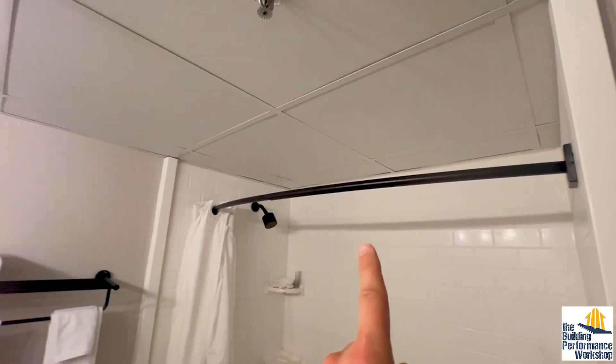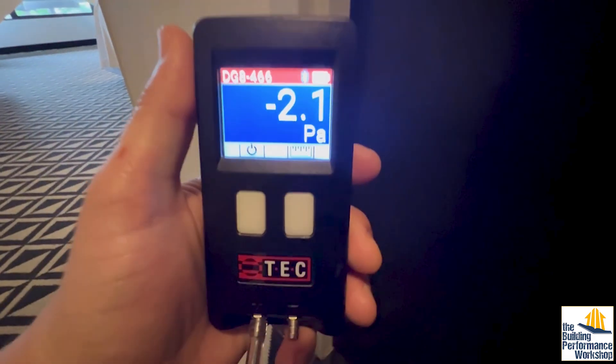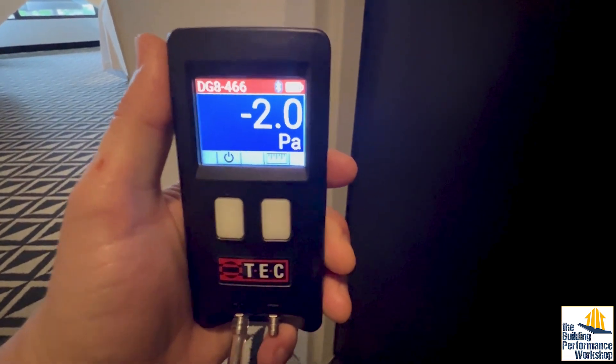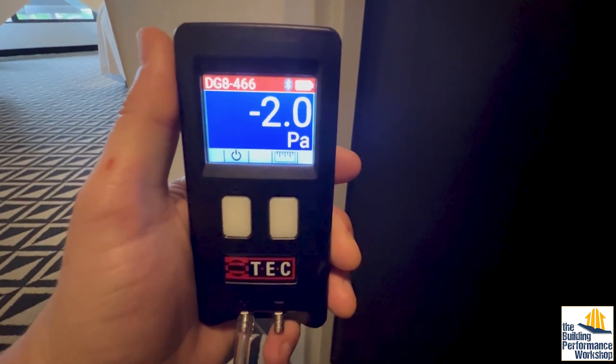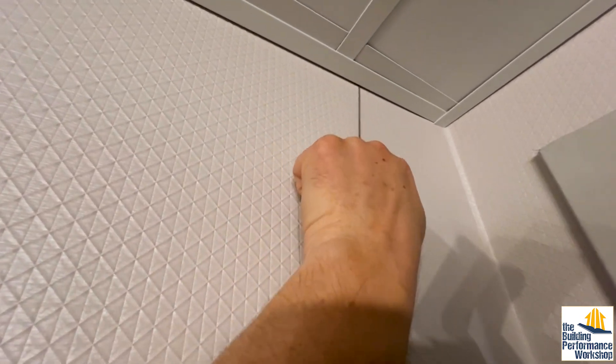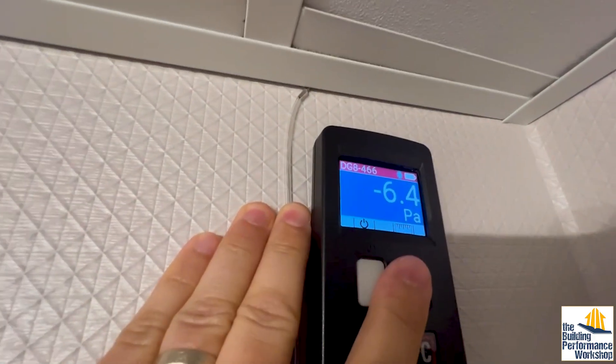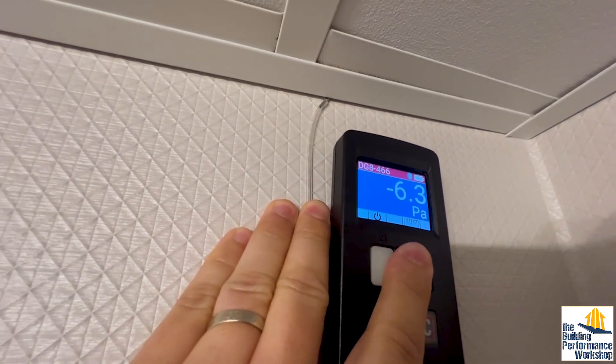That's not exactly what's going on, and there's a really cool fix for this. If there were no exhaust fan, that bathroom would be pressure neutral. But when I drop a hose into the room and measure with my pressure gauge — this is a TEC DG8 — you can see that it is depressurized relative to the rest of the hotel room. And behind this acoustical tile ceiling, if we insert a pressure probe up there, we have a major depressurization. So let's go explore.